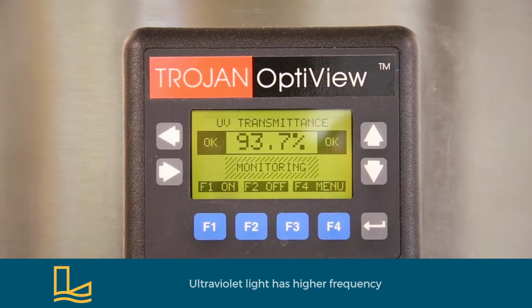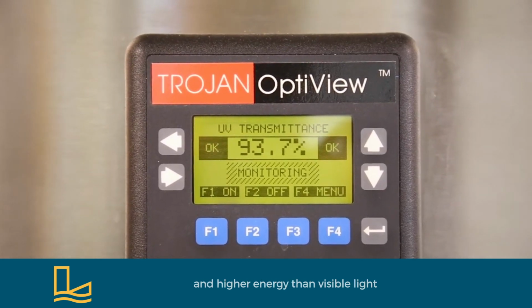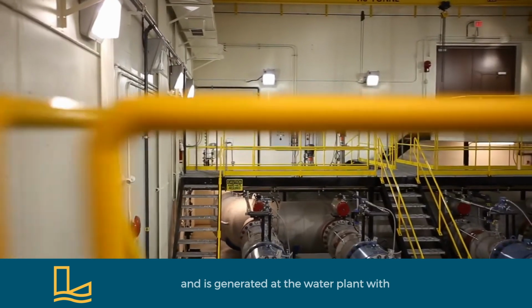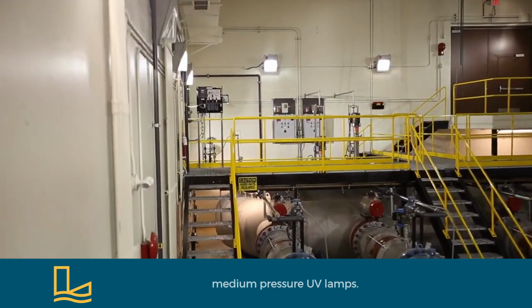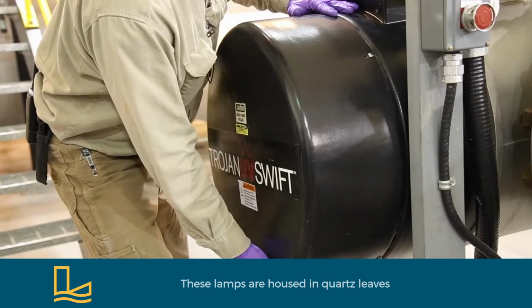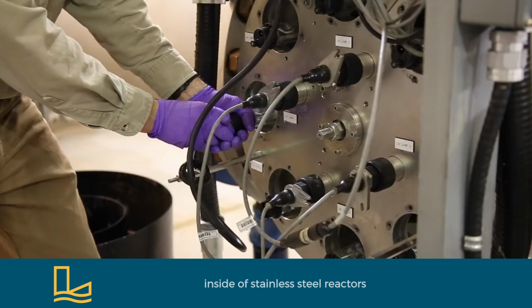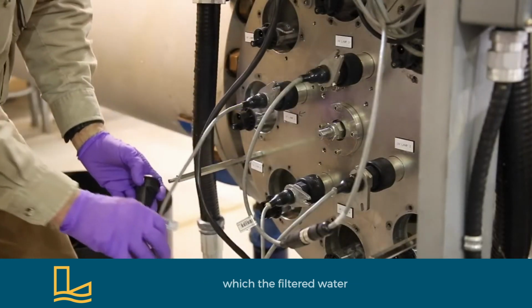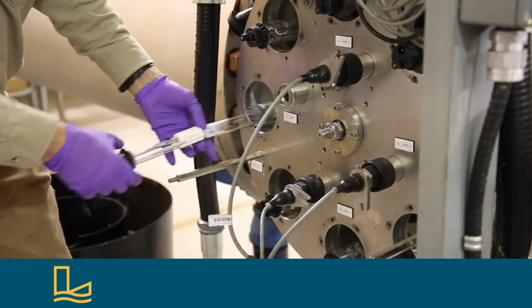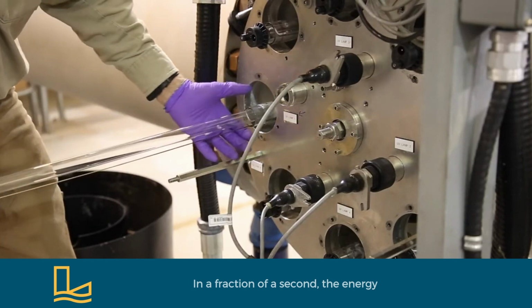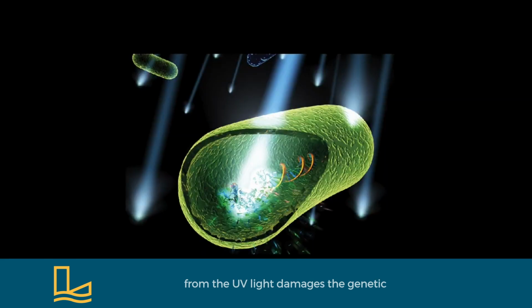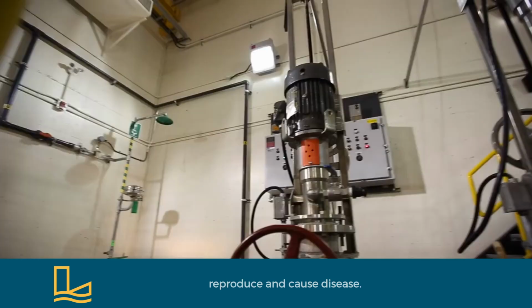Ultraviolet light has higher frequency and higher energy than visible light and is generated at the water plant with medium-pressure UV lamps. These lamps are housed in quartz sleeves inside of stainless steel reactors, which the filtered water passes through to be disinfected. In a fraction of a second, the energy from the UV light damages the genetic material of the protozoa, making them unable to reproduce and cause disease.